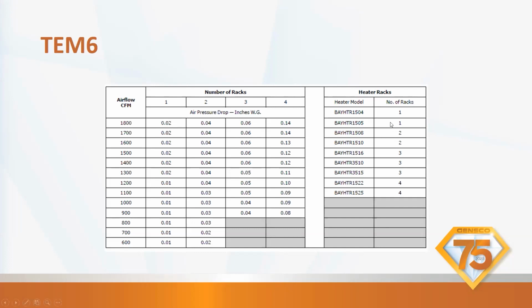And over here, there's also a chart that tells you how many racks for each different strip. And then you go over how many racks, whatever unit you have, go down to how many CFMs you're trying to go to. And that's what you have to deduct from your total to get the correct CFM. I know it's kind of a pain, but this is how you set it up to get it right on.